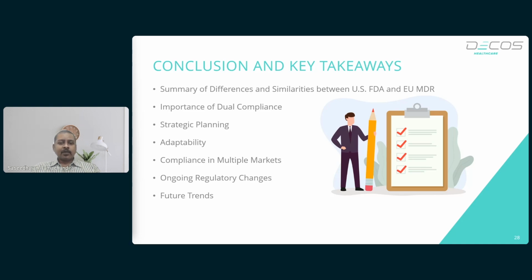Both frameworks require post market surveillance to maintain device safety. However, the FDA has specific reporting timelines, such as 30 days for adverse events, while the EU MDR has more extensive documentation requirements for serious incidents.